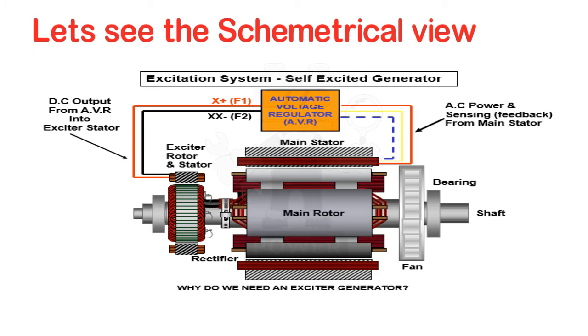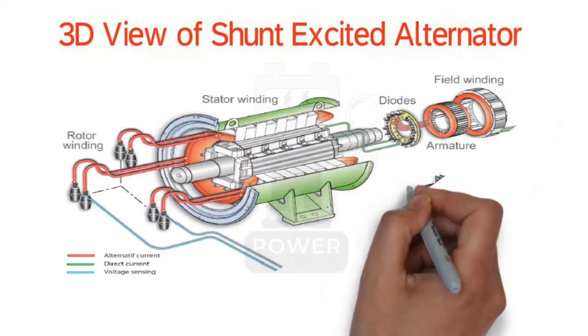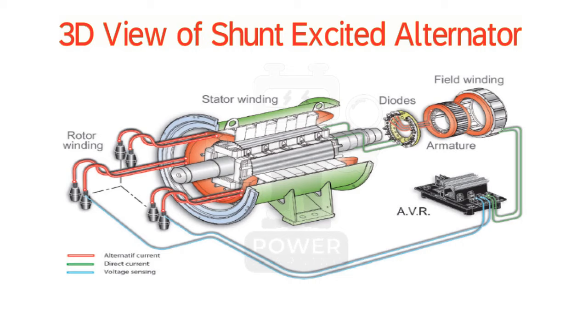This is the simple self-excitation system. Let's have a look at the 3D view of a shunt-excited alternator. Here you can see the field winding connected with the AVR DC supply, and two blue wires coming from the stator winding. The rotor is also present, and these two wires connect to the diodes, which connect to the main rotor windings. This type of shunt-excited alternator is also called a self-excited alternator.